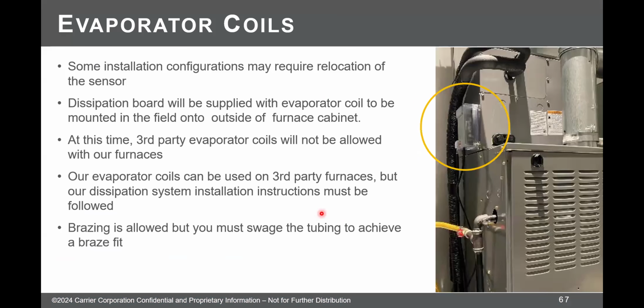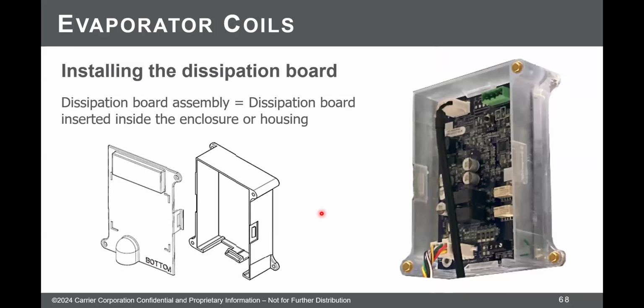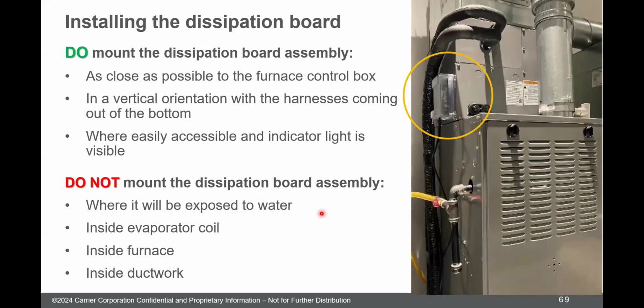It gets mounted separately. So for all the equipment, it gets mounted inside the equipment, except for furnaces. For some reason, furnaces don't get mounted inside. I don't know why. Maybe it voids the UL listing. I have no idea. I've gotten different answers and none of them sound plausible. So it just can't. It cannot be mounted in water. That seems obvious. It cannot be mounted in the evaporator coil. There wasn't any space. Can't put it inside the ductwork. Didn't want to do that anyway. And you can't mount it in the furnace, which I said is weird. I don't know why.